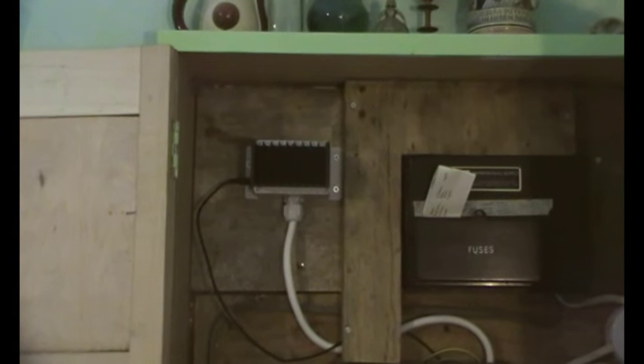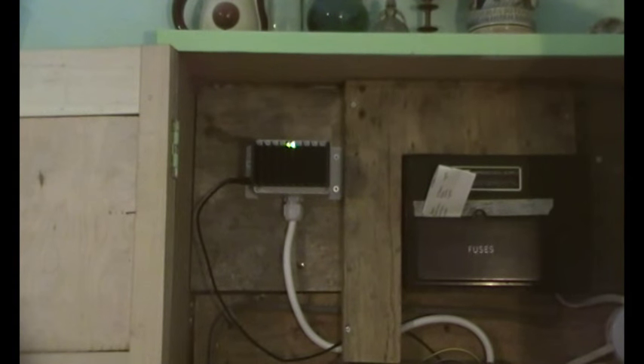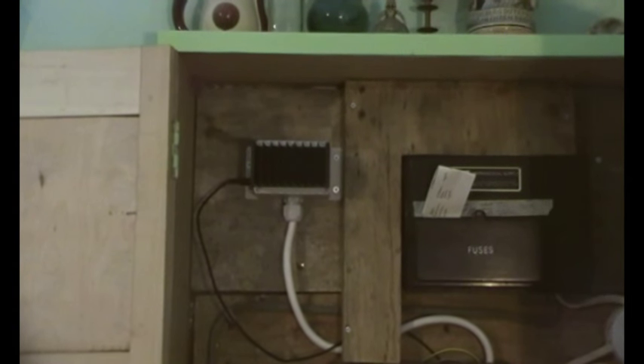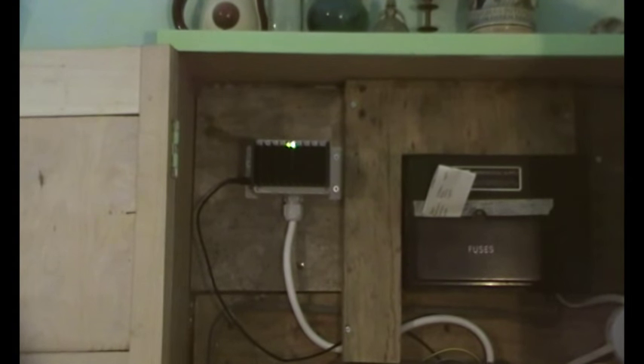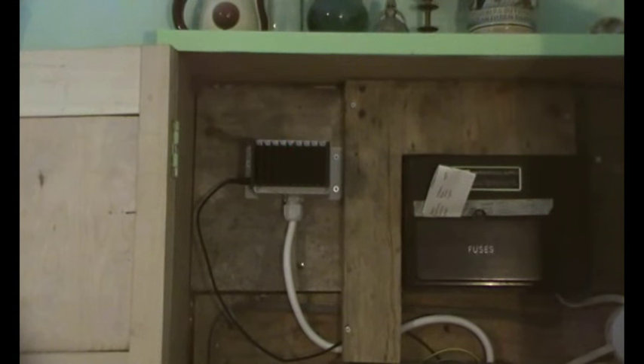If it flashes once every two seconds, then the current clamp should be reversed. I reckon we need to reverse the current clamp.